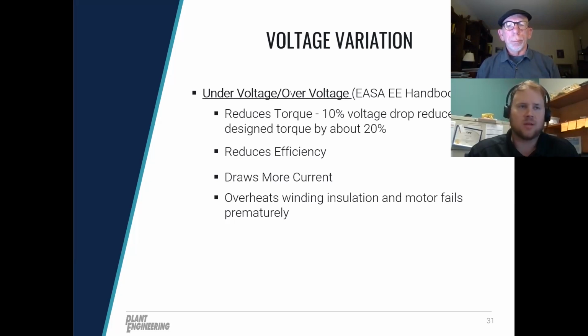According to the electrical engineering handbook, if you look at a 10% voltage drop, then motor design torque could be reduced by approximately 20%. So in general, to sum it all up, when you have lower voltage supplied to the motor, the motor is going to need more current to output the necessary torque and speed for your specific application. So higher current draw, we've talked about it a little bit earlier. What does it lead to? Overheating, and then of course, eventually motor failure.